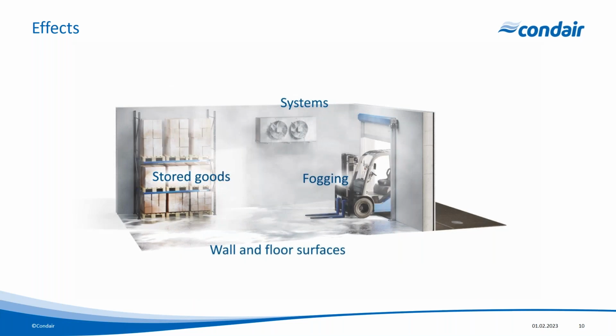Fogging is also very common, and typically fogging is going to occur when the relative humidity is very high and we're typically 2 degrees C below dew point. Fogging will occur when moisture has saturated the air and it's suspended in the air. And this gives you a problem if you're moving heavy machinery around. It is a health and safety issue. You've got stored goods on pallets, you've got forklift trucks, you've got people moving around, and even though they're in high vis, fogging can cause a dramatic loss of visibility within that store. So getting rid of that fogging is very, very desirable.